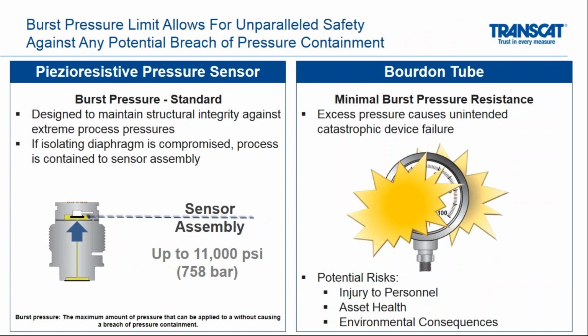Another one, so I mentioned how overpressure is simply what happens at irreversible damage. There's another piece, and that's burst pressure. That's when all of a sudden the pressure is so big that it escapes. With piezo-resistive technology, those two isolators allow you to go up to 11,000 PSI, regardless of what the span is. And up to 11,000 PSI, there won't be a rupture of some sort. It's designed to maintain its integrity up to this point, and it makes it very safe for your workers and for the applications you put a gauge in.